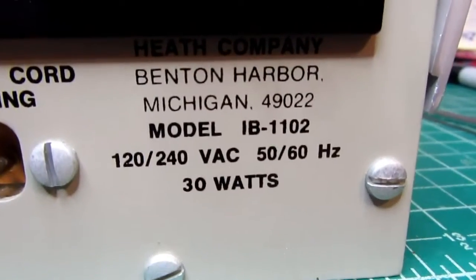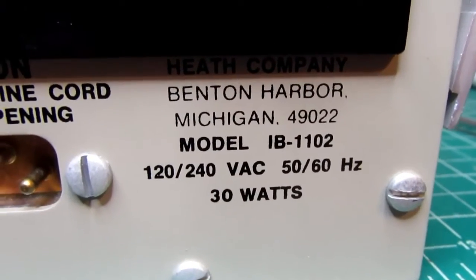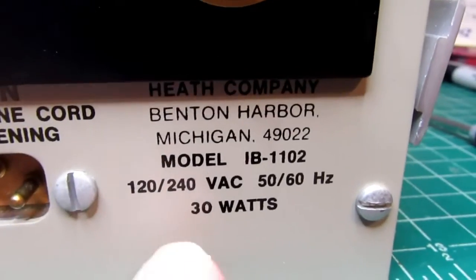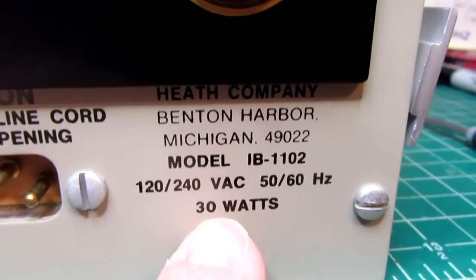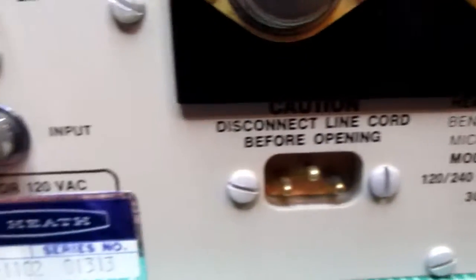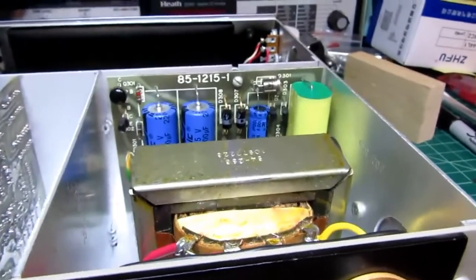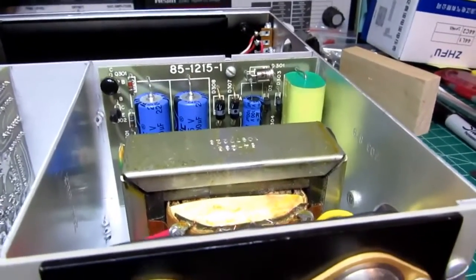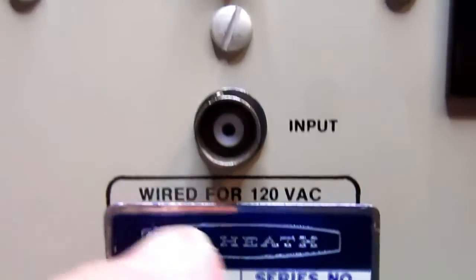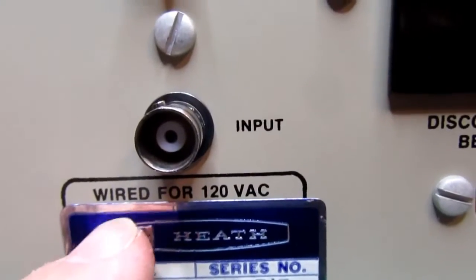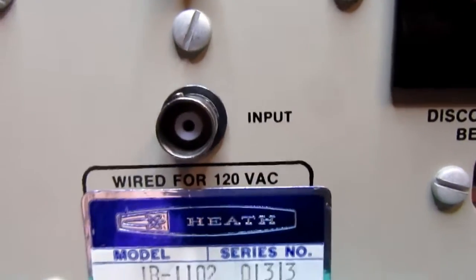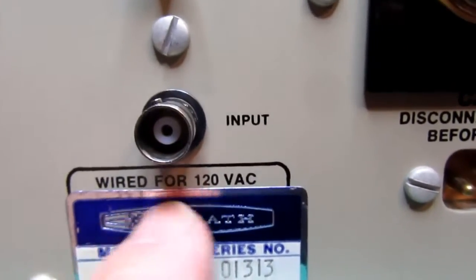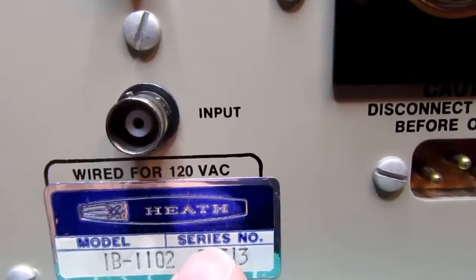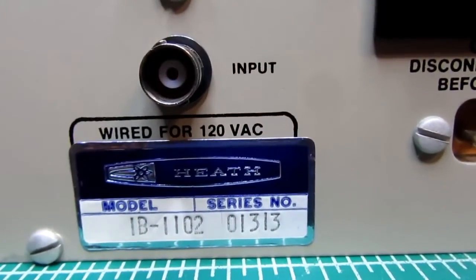And then of course we have the model number and its power capabilities in terms of frequency and voltage and how much wattage it uses. And you have to hardwire this for the line voltage. There's not an internal switch. You have to wire the transformer one way or another. And so there's a graphic on the rear panel that says wired for 120 volts and also wired for 240 volts, and you put the product sticker over the one you're not wired for, so it covers up.